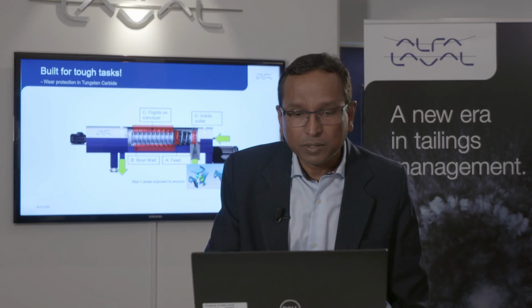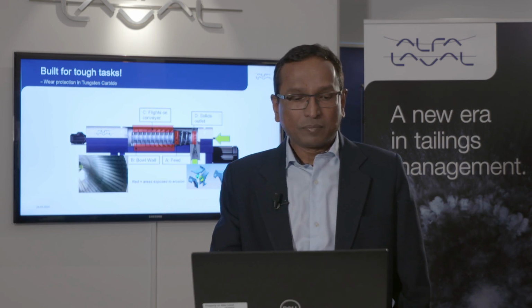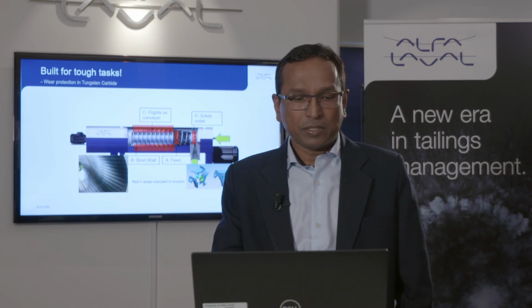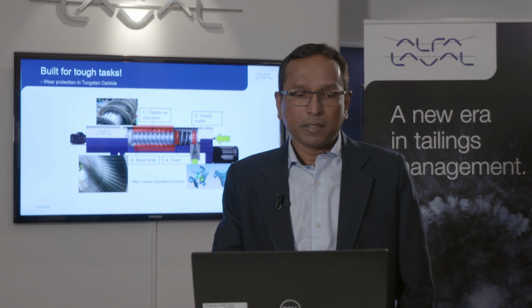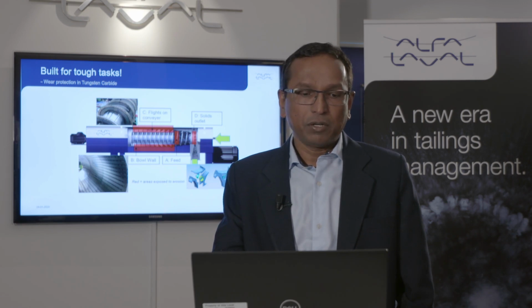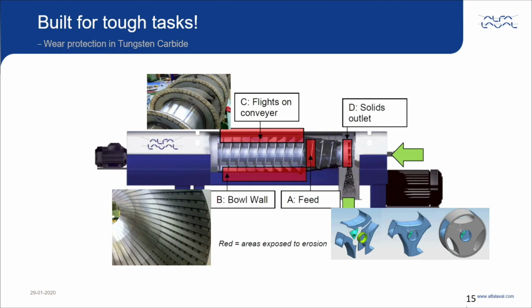We talk about the solids discharge port, the wear liners on the bowl, the conveyor protection consisting of tungsten carbide tiles across the full length of the conveyor, and the solids discharge port. Yeah, and the first part here that I spoke about is the feed zone. By mistake, I said solids discharge.